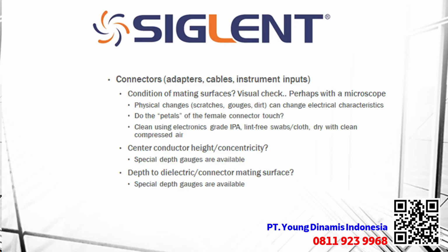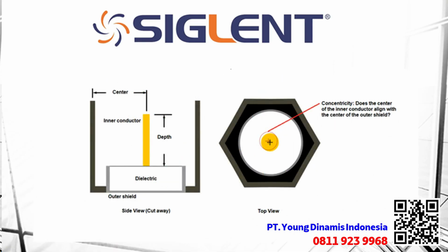We also want to clean using an electronics grade IPA or isopropyl alcohol, lint-free swabs and cloths, and then we also want to have some dry, clean, compressed air available. We can also take a look at the center conductor height and concentricity of our connectors. There are special gauges available for that. And then there's the depth of dielectric and connector mating surfaces, again, also available with some special depth gauges. We're not going to go into detail of that, but I did want to bring it up because it is very important. Here you can see the concentricity and some of the physical measurements that we may need to make on a specific type of adapter or connector.